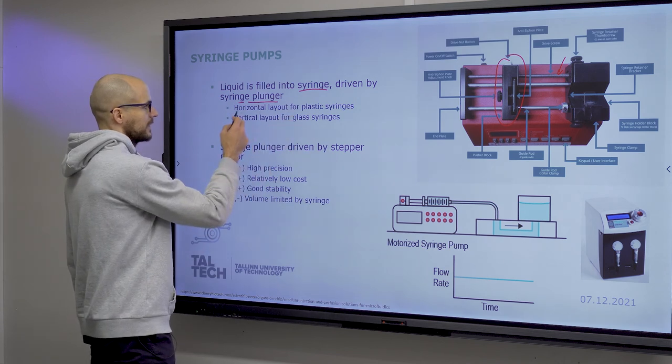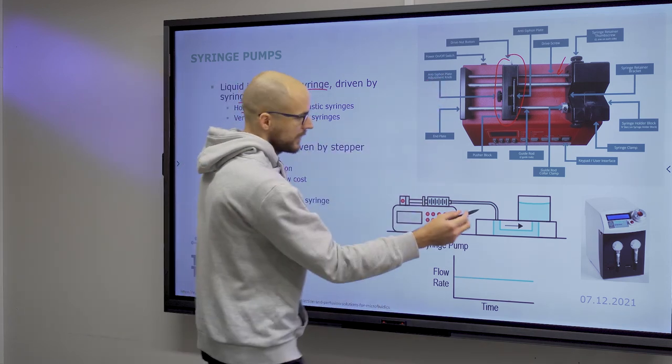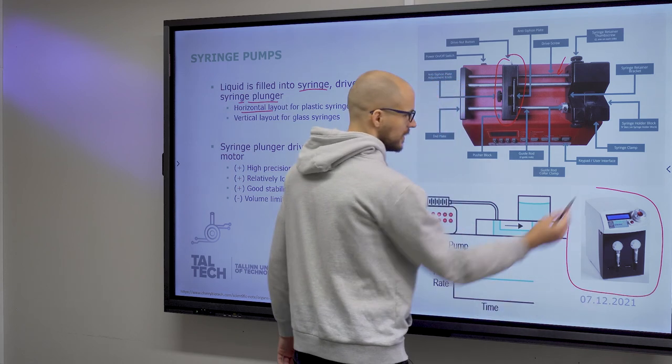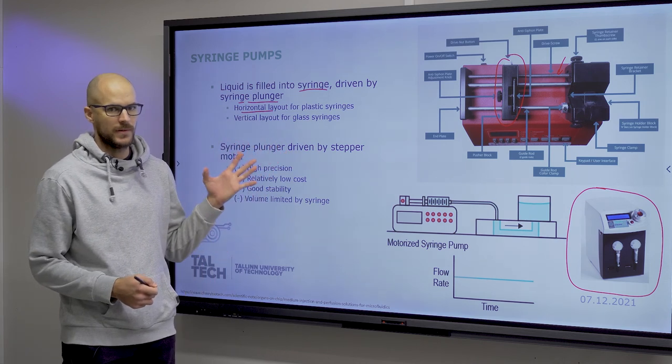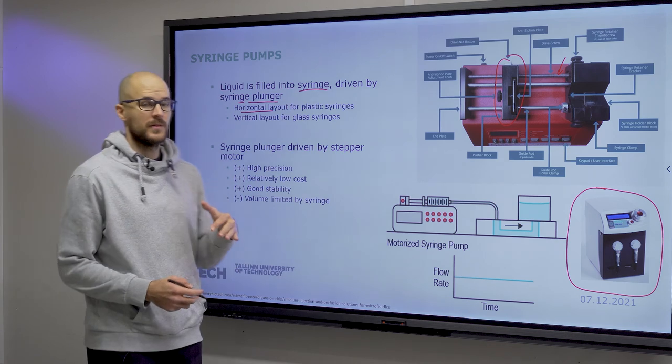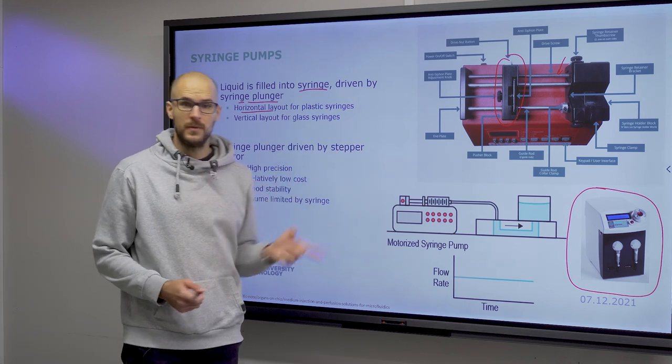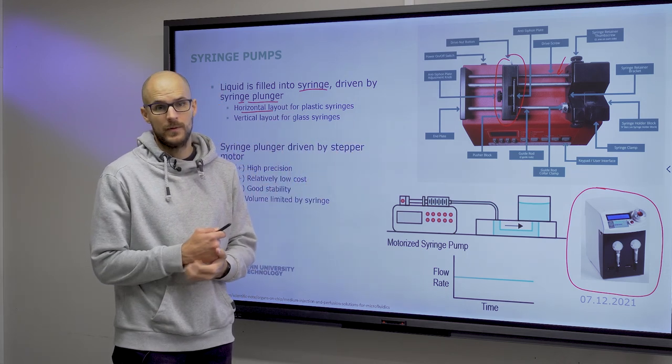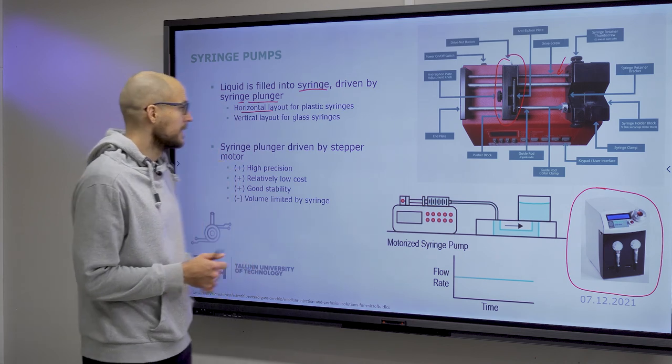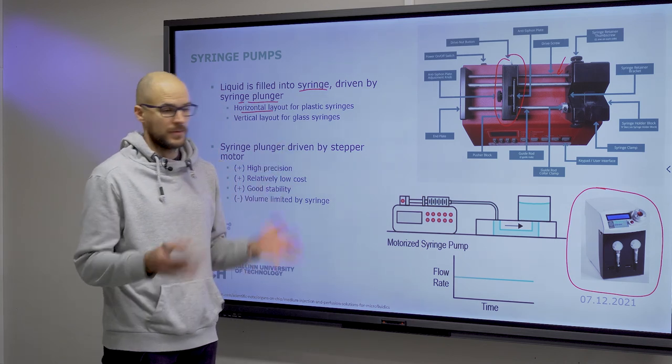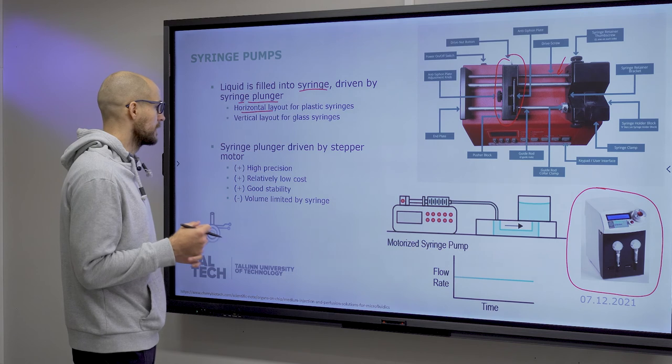For plastic syringes, most typical would be a horizontal layout like you see above. For glass syringes, typical would be a vertical layout where the glass syringes act like pistons, and precision is somewhat better. However, you can also use glass syringes with the infusion pump layout, for instance Hamilton glass syringes. That is a more precise setup, because for plastic syringes there is always the matter of flexibility of the plastic that will take down from the precision.